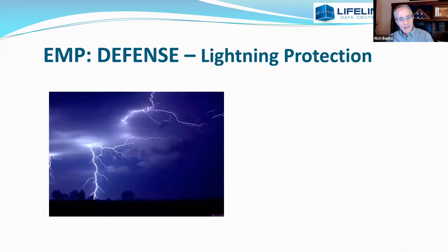In addition to the mega-dollar filters, I need to discuss lightning protection because I've talked about how well everything is earthed. You protect against lightning by attracting it to lightning rods and sending it to earth. We live in fear of a backfeed coming back up through our other earthing systems, feeding into power equipment, blowing up through that shield. There is no protection against an actual direct lightning strike — it is a force of nature that cannot be dealt with. Dr. Radasky made that real clear. In our 19-and-a-half-year history of operating a data center, we've had one direct strike and the damage was immense. It is the one outage we have had in our entire history.